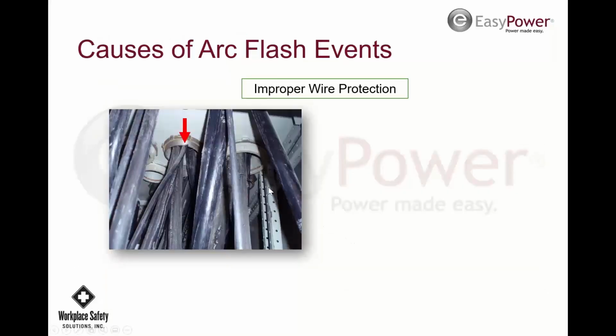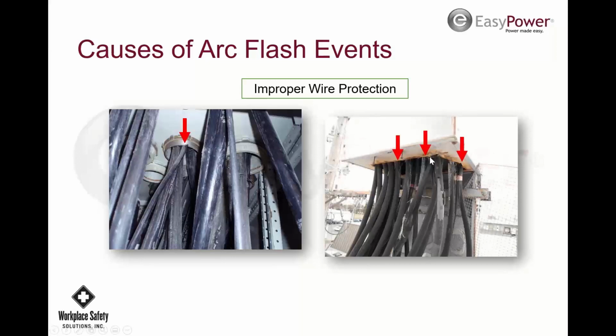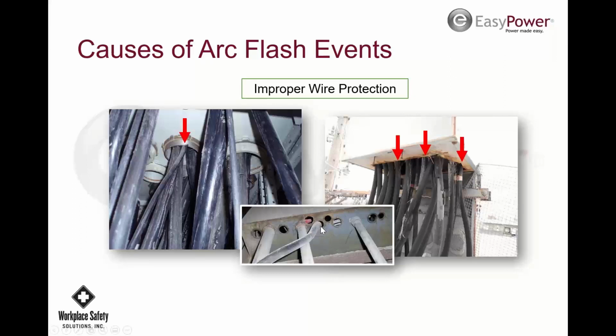Here's some things that cause arc flashes. So they missed the bushing. They forgot to put it on there. Now you got the wire skinned. So that's going to be an arc flash happening anytime. Same thing here is going to happen, right? So these wires are old, and there's bare metal that they can cut up against, and it's a matter of time. It's going to happen. Any kind of, where you have abrasion protection, you need abrasion protection for these things. Got to have a connector, and you can't use flexible wire for temporary wiring, for permanent wiring anyway.